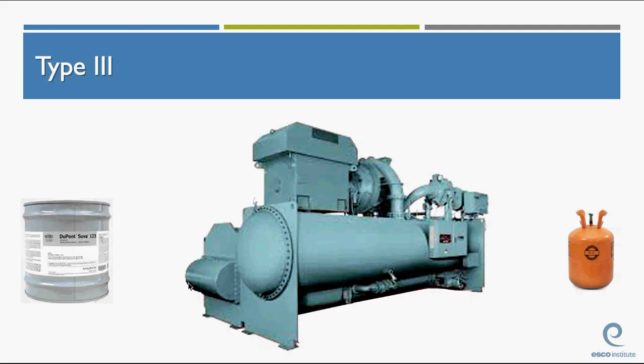Is that a big compressor in the middle? This is a big chiller. Now, let me tell you a little bit about what's going on here. In type 3 systems, the evaporator, which is the chiller barrel, is probably this portion right here. I can't see all the piping. The evaporator has refrigerant in tubes in here. We talked about a tube-in-tube chiller. Your tubes are accessible by taking all the bolts off the end after the unit's drained and refrigerant is recovered. You have a big centrifugal compressor up here. This is an open drive compressor. Your drive motor is in this whole big container right here.